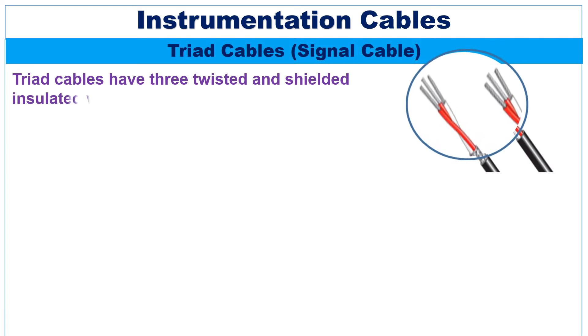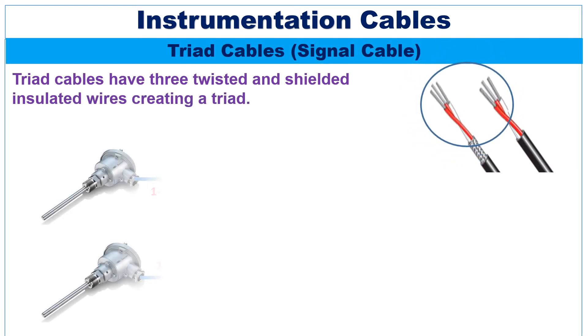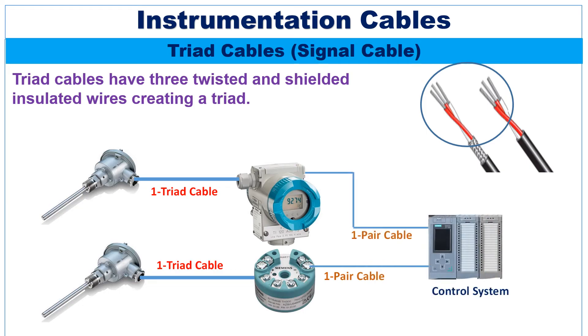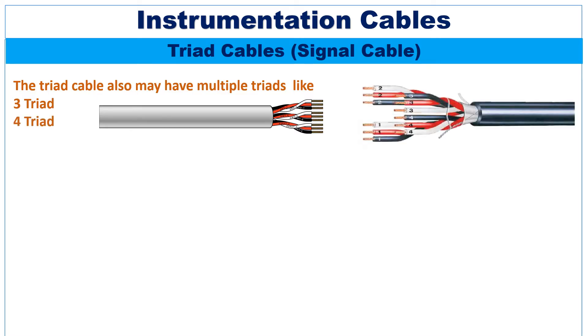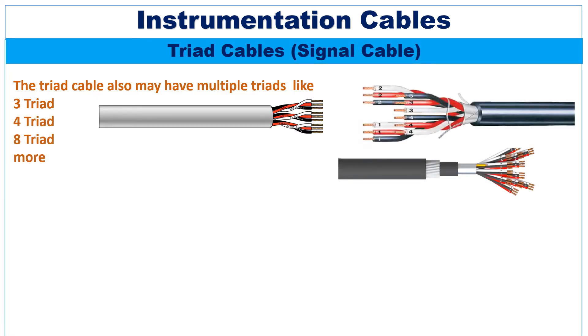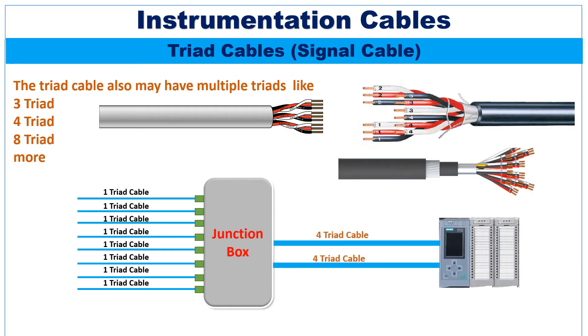The next signal cable is the triad cable. Triad cables have three twisted and insulated wires creating a triad. The triad cables are laid between RTDs and temperature transmitters. The triad cables may also have multiple triads, like 3, 4, or 8 triads, and multi-triad cables are used between the junction box and control system.